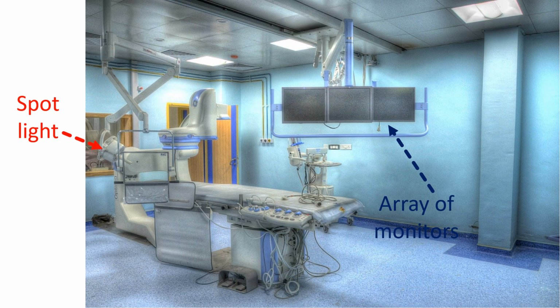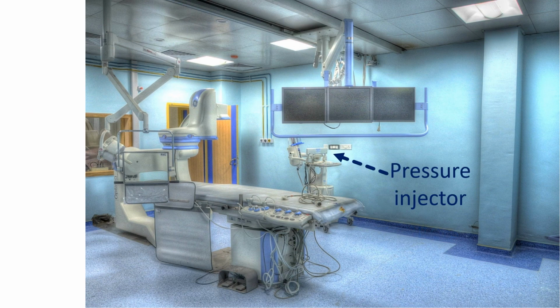One will be live fluoro, another can be used as a roadmap with a previous frozen image. Third monitor will show the pressure tracings and ECG. Continuous monitoring of ECG and catheter tip pressure are essential to ensure patient safety. An additional defibrillator monitor will also be there with defibrillator paddles kept with electrode jelly for immediate defibrillation if needed. A pressure injector is used to inject radio contrast for left ventriculography and aortography at graded speed, which is adjustable as per need. Infusion pumps, resuscitation tray, medication tray, racks for catheters and devices are other things not shown in this image. When electrophysiology procedures are done, electrophysiology recorder, stimulator and ablator are additionally needed.